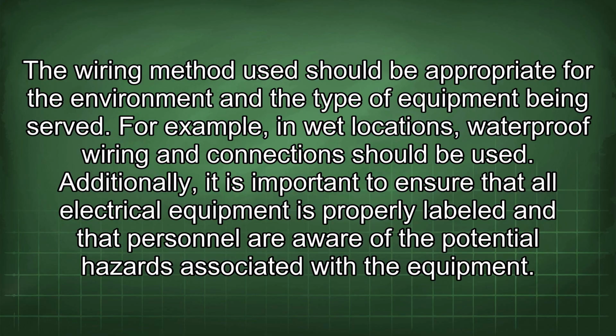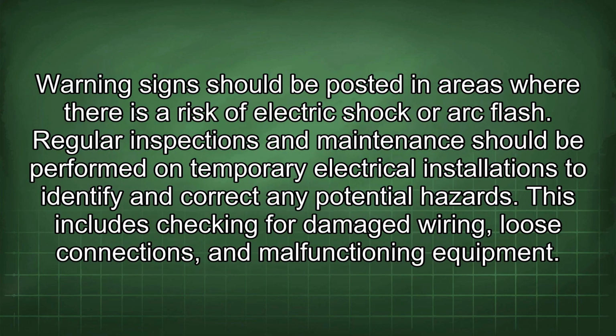For example, in wet locations, waterproof wiring and connections should be used. Additionally, it is important to ensure that all electrical equipment is properly labeled and that personnel are aware of the potential hazards associated with the equipment. Warning signs should be posted in areas where there is a risk of electric shock or arc flash. Regular inspections and maintenance should be performed on temporary electrical installations to identify and correct any potential hazards. This includes checking for damaged wiring, loose connections, and malfunctioning equipment.